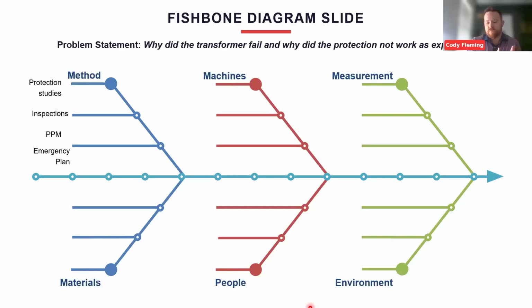Okay, when we're restored, power's restored, we're good. We have these two problems that you stated: the transformer failure and the seeming lack of coordination across your switchgears. So what do the inspections look like? Are there rounds? Did anything get missed? Or how often are they inspecting these transformers? And I've seen a couple different transformer configurations, obviously. I've seen ones oil filled with external fans. I've seen the ones that you have here, which are radiator style with natural circulation. So are they cleaning them? Are they inspecting the cabinets and whatnot? So those are the kinds of things that I'm going to start thinking about and start asking questions about for method. And I'll turn it over to Jonathan for protection.